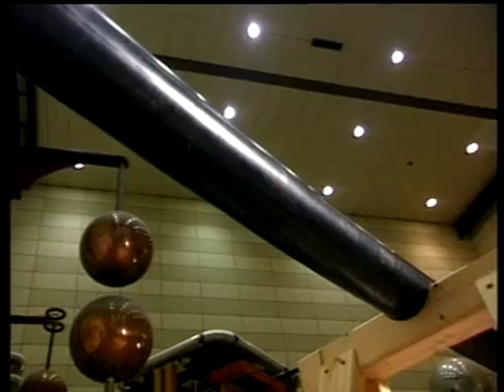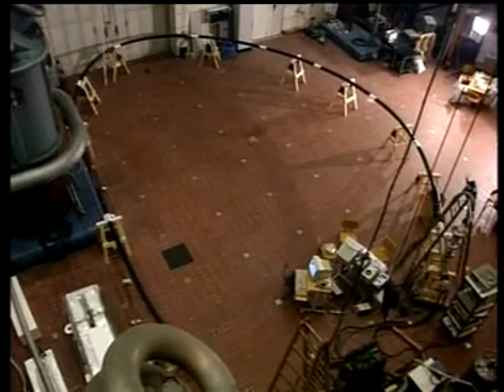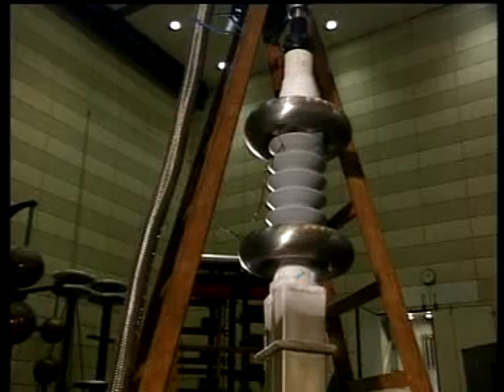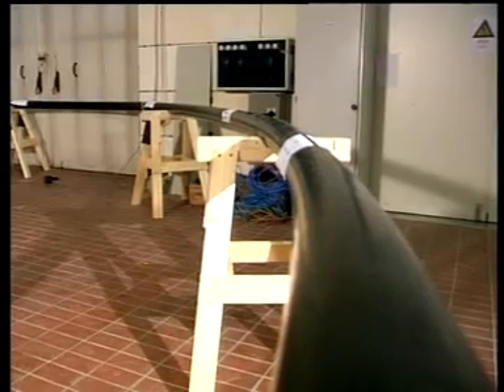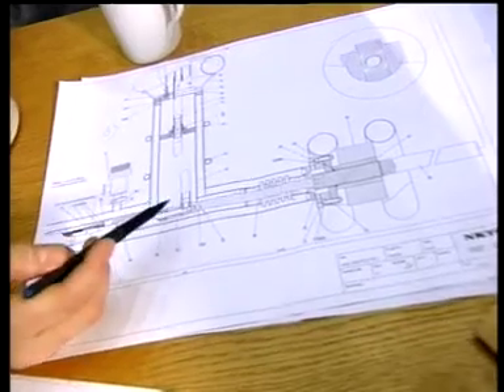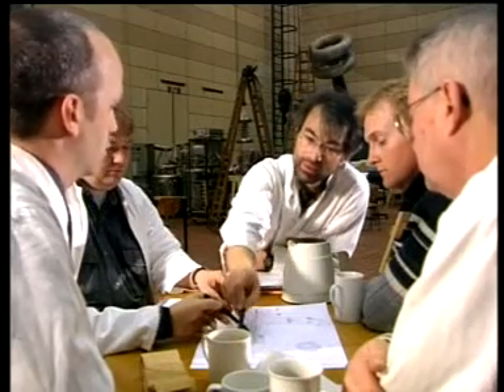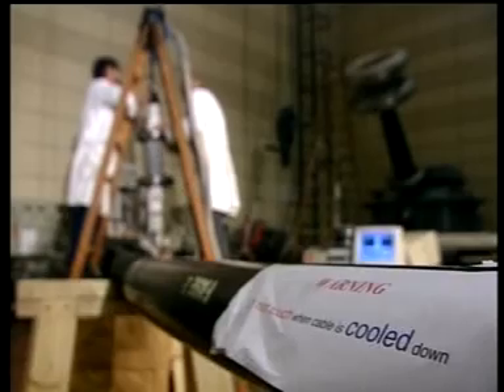This cable system is rated at a voltage of 36 kilovolts and a current of 2 kiloamps. It's designed to link two medium-sized transformer stations in a city environment and can transport a power of 100 megawatts. The superconducting cable is much lighter, and the superconducting cable is more environmentally friendly.